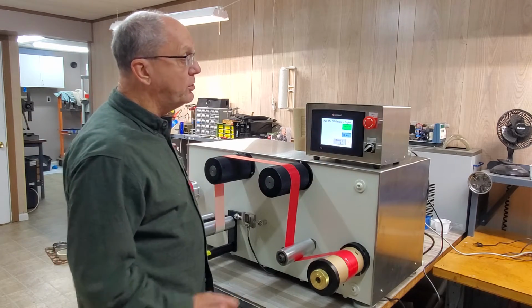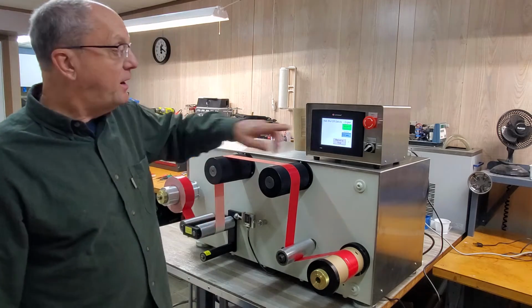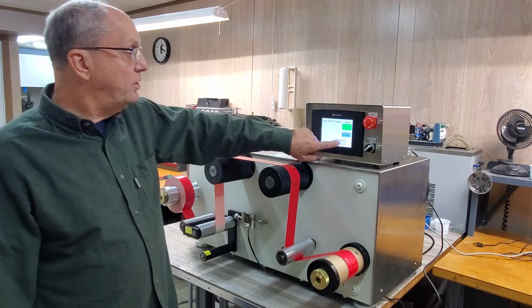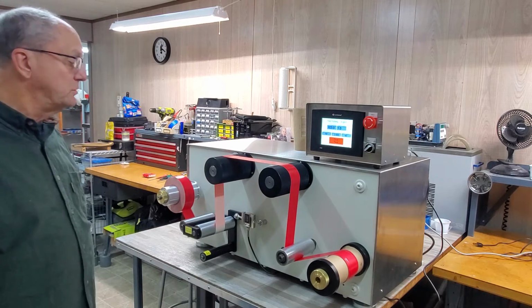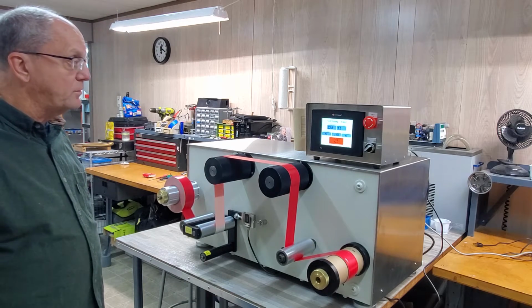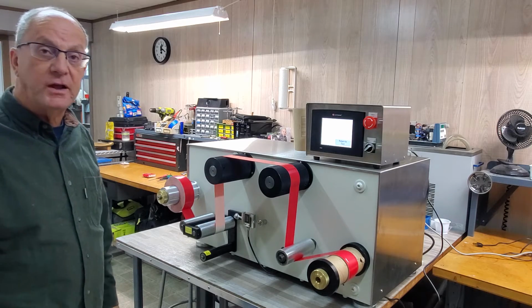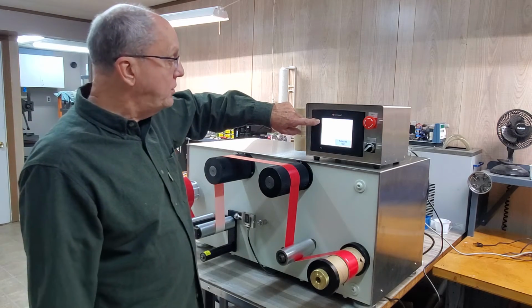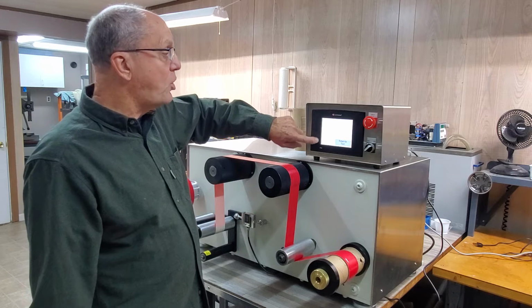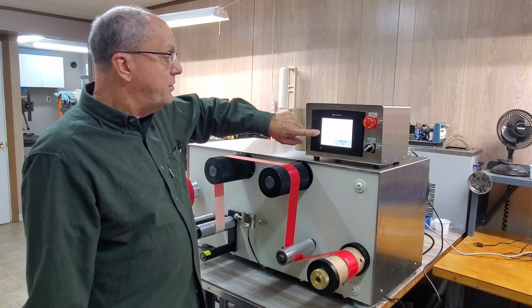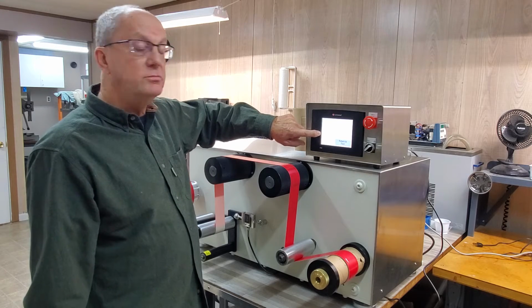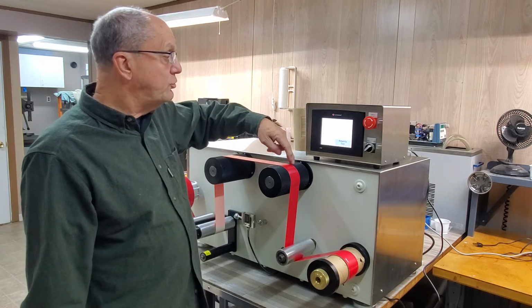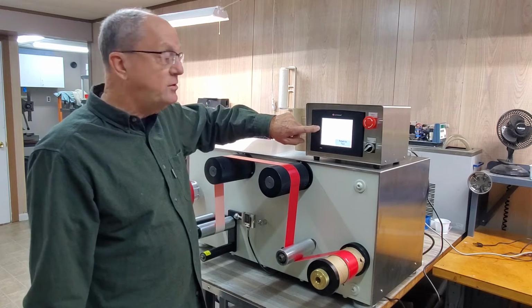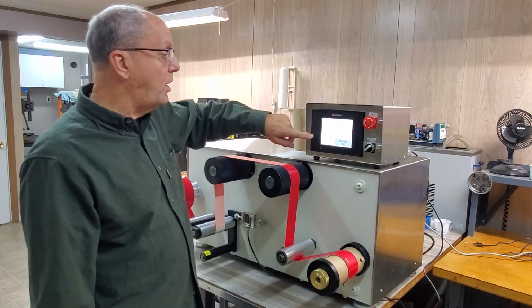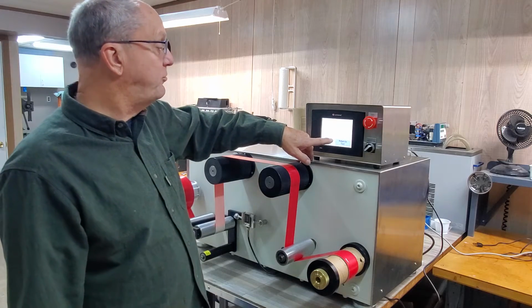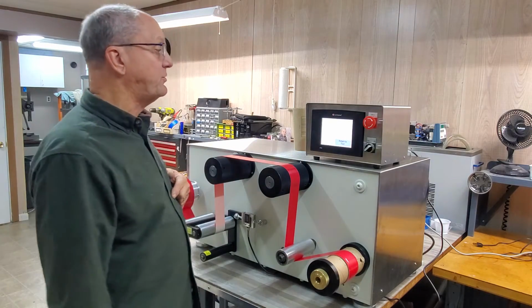The first mode is what we call time shut off, and I have that set for 5 seconds, and that merely works like this. It runs for 5 seconds and it stops. Now at the conclusion of the test, we are displaying some parameters here, the min and the max and the average tension that was measured during the test, and also the length and where the maximum occurred on the roll. In our case here, our maximum force was a half a foot into the test.